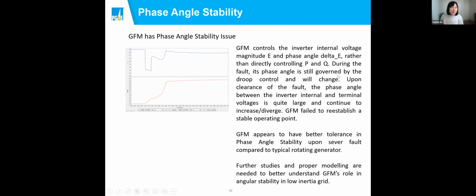Another thing I want to highlight, but won't spend a lot of time on, is that grid forming inverters do have phase angle stability issues. This is just a test to show that post-contingency, because during the contingency the system conditions are very severe, the phase angle has already risen to a very high level. So post-contingency, after the fault is cleared, the phase angle cannot be stabilized. The grid forming inverter failed to reestablish a stable operating point, and hence there is this phase angle stability issue associated with the grid forming inverter.